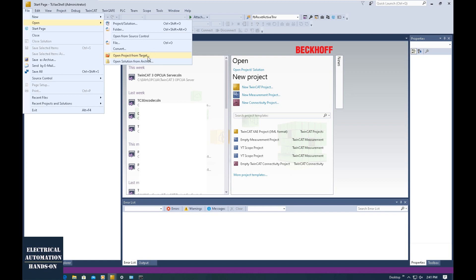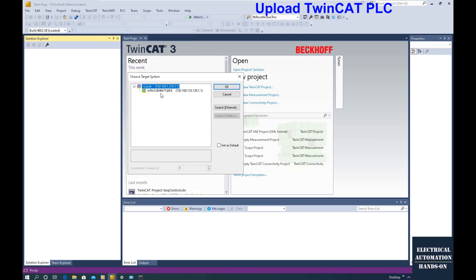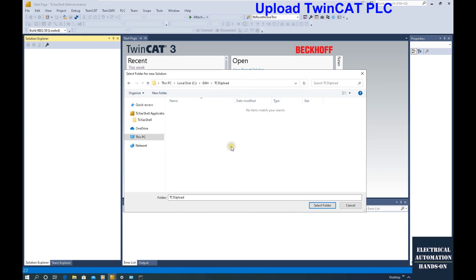Let's hit 'Open Project from Target'. From this list it will show all the online controllers your software can connect to. Now it shows I'm connecting this remote PLC. Hit OK. After this, it will ask which directory to allocate the project. You better create one folder — the folder could be named with a date, time, or some specific name. So I name it 'TwinCat 3 Upload'. Hit 'Select Folder'. The project will upload to this folder. This process could take around one minute.